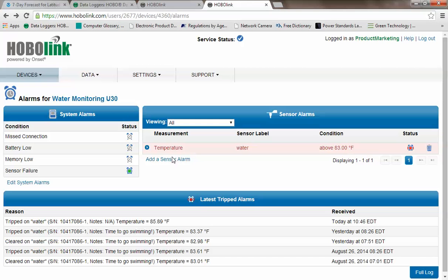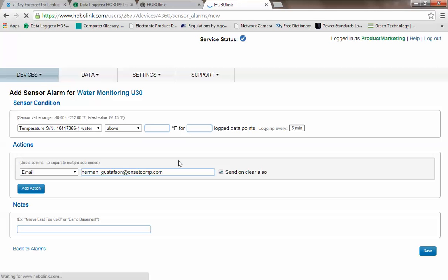And if you wanted to add a new sensor alarm, you would select add a new sensor, select what sensor you want to have that alarm set for, and then select what your threshold might be, either above a specific temperature, below a specific value, I should say, or outside of a specific range, you can do that. And you can add as many as you wish.